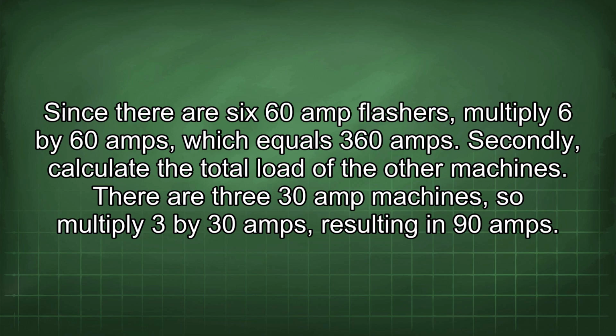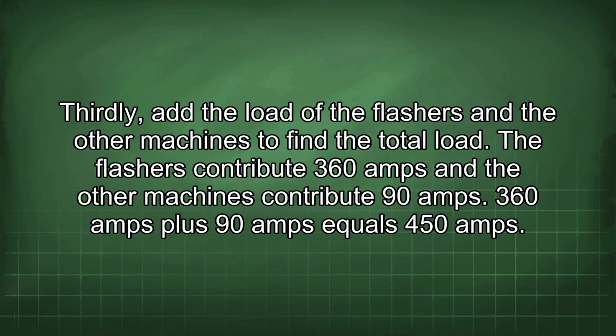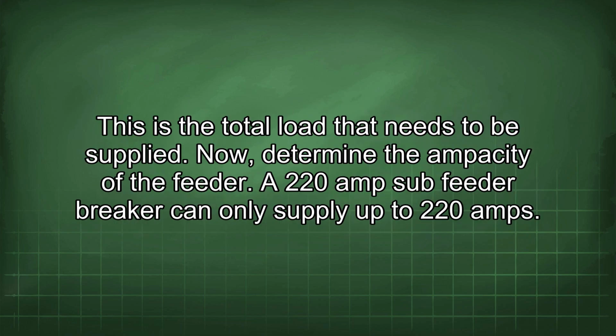Secondly, calculate the total load of the other machines. There are 3 30 amp machines, so multiply 3 by 30 amps, resulting in 90 amps. Thirdly, add the load of the flashers and the other machines to find the total load. The flashers contribute 360 amps and the other machines contribute 90 amps. 360 amps plus 90 amps equals 450 amps. This is the total load that needs to be supplied.